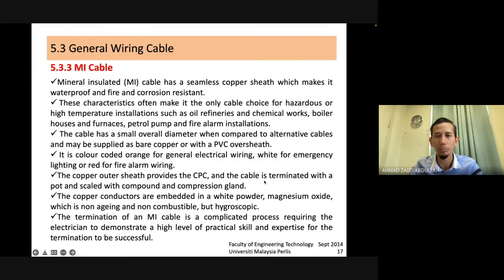Then the cable is terminated with a pot and sealed with compound and a compression gland. It has accessories related to the MI cable. It cannot use the others because they are different, and we must use a compression gland. We must compress the connection. Then the cable is embedded with white powder. If you cut the cable, you can find white powder, magnesium oxide, which is non-aging and non-combustible but hygroscopic.